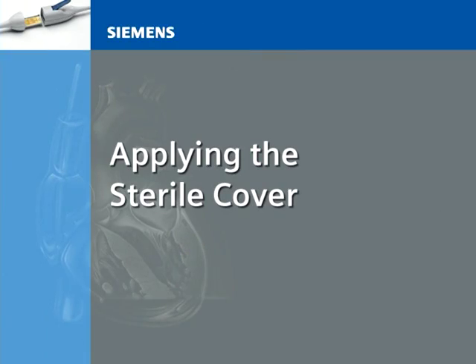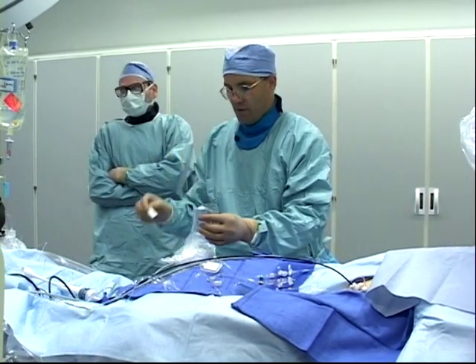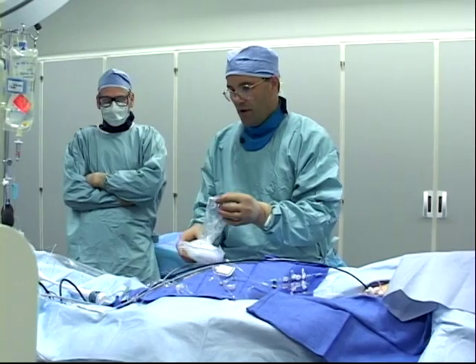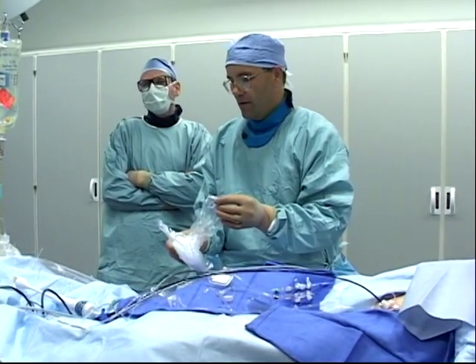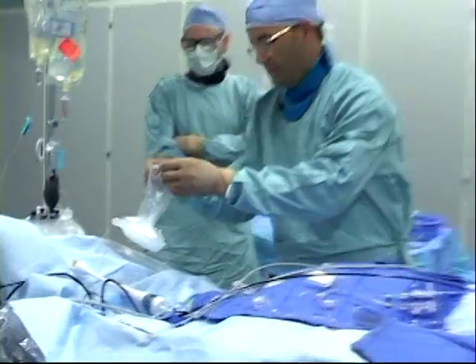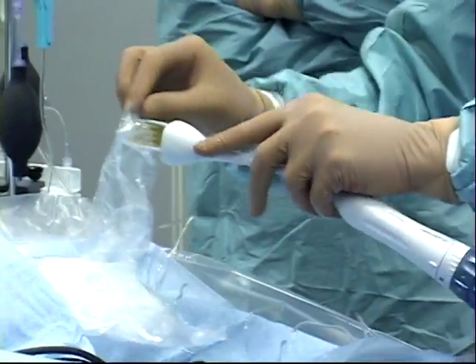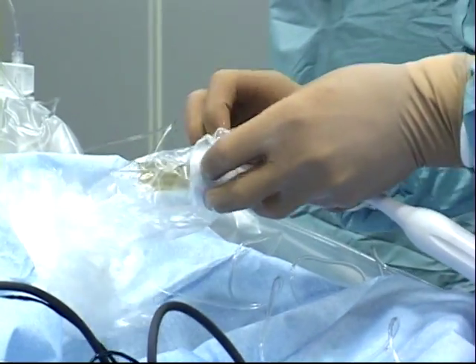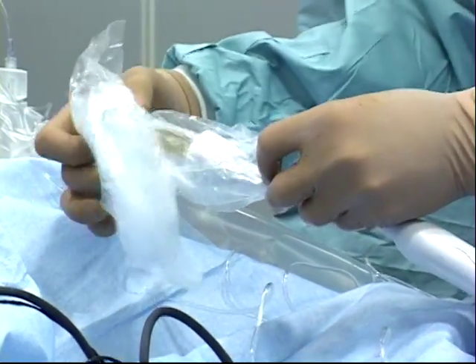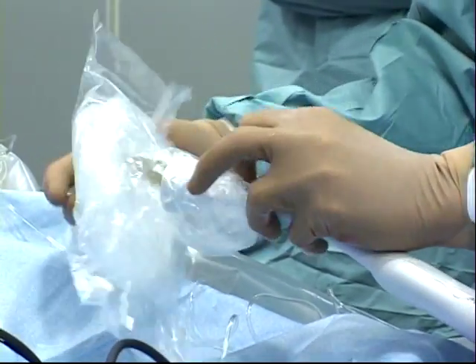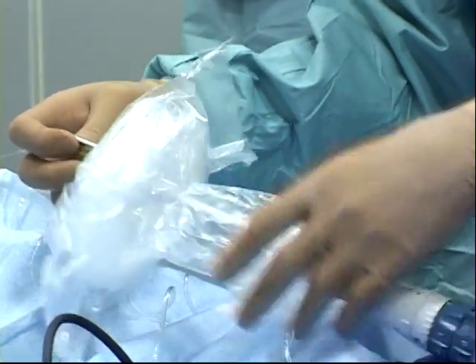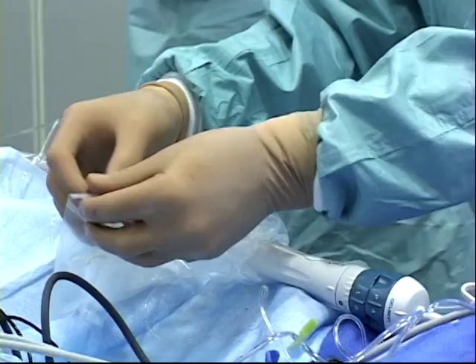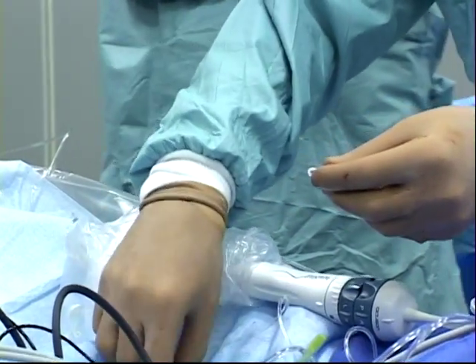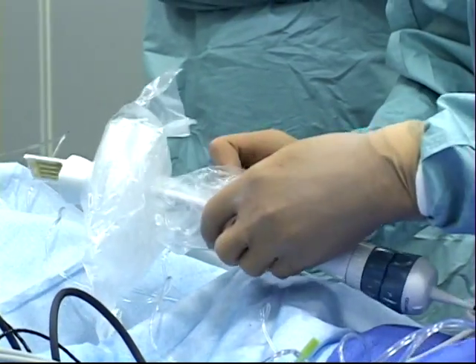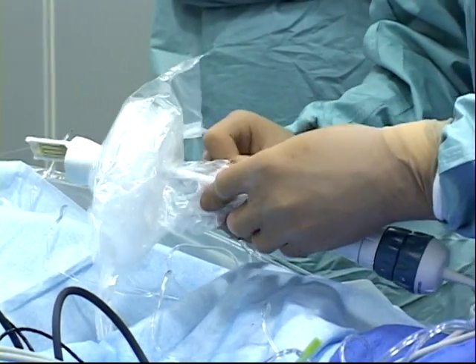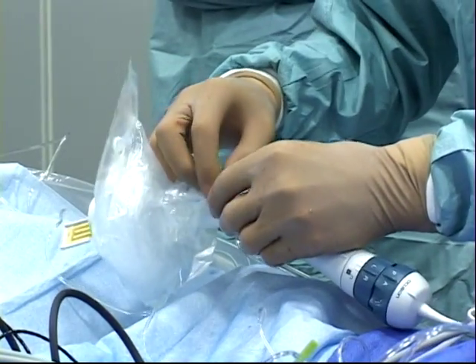Applying the sterile cover. Applying the sterile sheath requires 2 people, one within the sterile field to prepare the catheter, and the other outside of the sterile field that will connect the AcuNav catheter to the SwiftLink connector. The person within the sterile field holds the ultrasound catheter by the handle and slides the unrolled end of the sterile sheath over the interconnect tab and the base of the catheter. The rolled end of the sheath should rest on the base of the catheter, leaving the interconnect tab exposed. Fasten the unrolled tip of the sterile sheath to the catheter extender near the base of the catheter handle. Be sure the sterile sheath is away from the interconnect tab so that the tab is exposed.